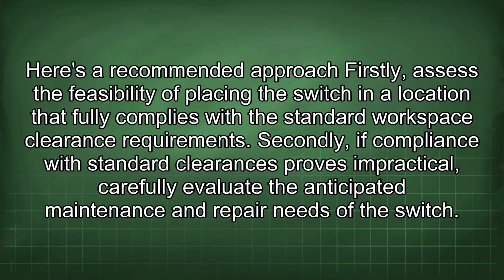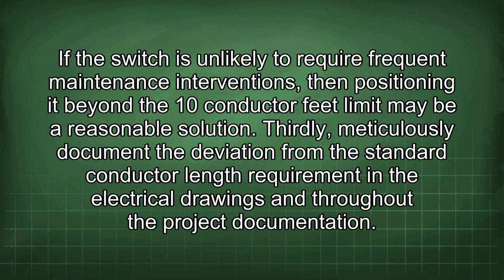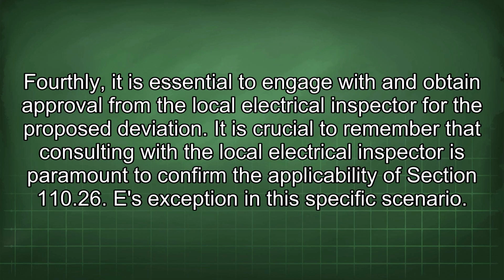Firstly, assess the feasibility of placing the switch in a location that fully complies with the standard workspace clearance requirements. Secondly, if compliance with standard clearances proves impractical, carefully evaluate the anticipated maintenance and repair needs of the switch. If the switch is unlikely to require frequent maintenance interventions, then positioning it beyond the 10 conductor feet limit may be a reasonable solution. Thirdly, meticulously document the deviation from the standard conductor length requirement in the electrical drawings and throughout the project documentation.